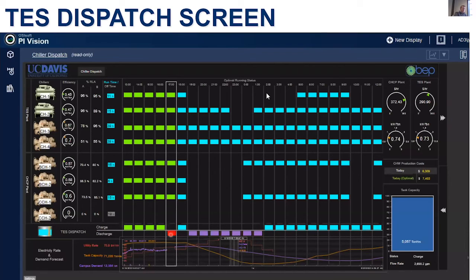It gives them a red box if it's a little off. There was a little bit of an issue here, but they've run it perfectly, and then they're going to shut all the chillers off at the exact right time so the campus goes into discharge. We couldn't do that without a really nice load forecast and without nice engagement for the operators to follow. And this has to be right. If this is wrong, the operators are going to lose faith in it pretty quick, and we're done. When you're dealing with facilities, folks, trust is key, and maintaining trust is key. So we have the unfun job of having to be right 95% of the time.